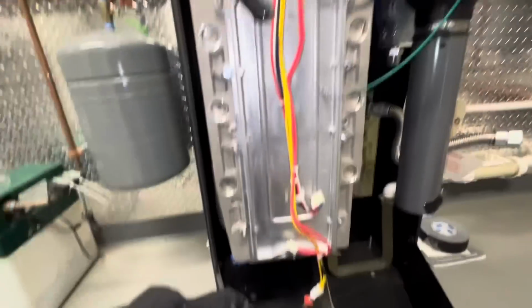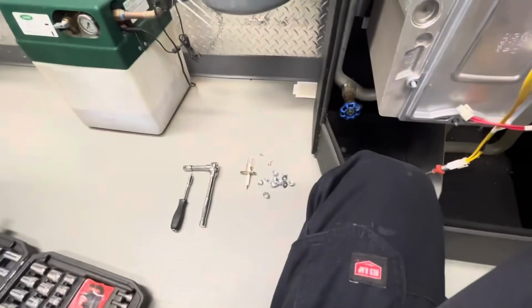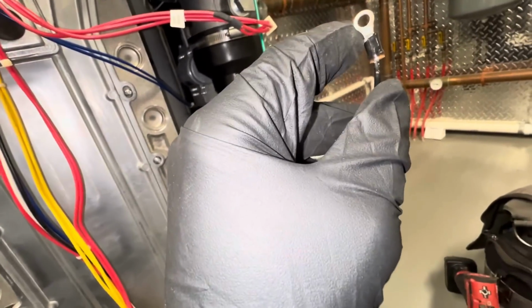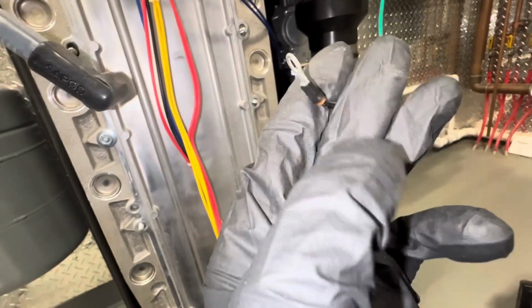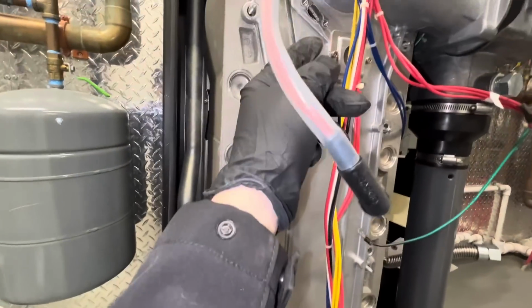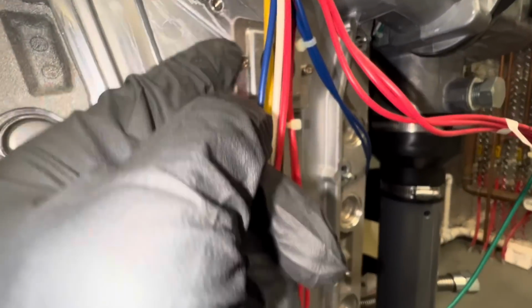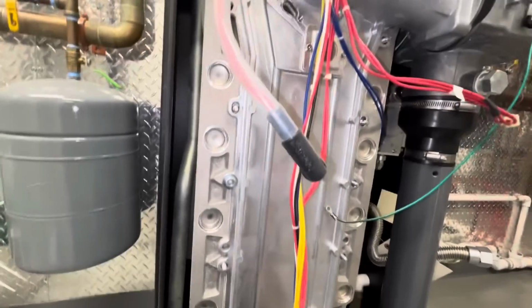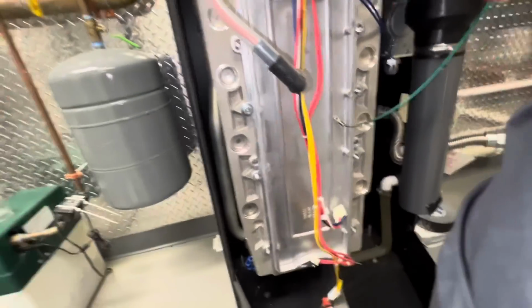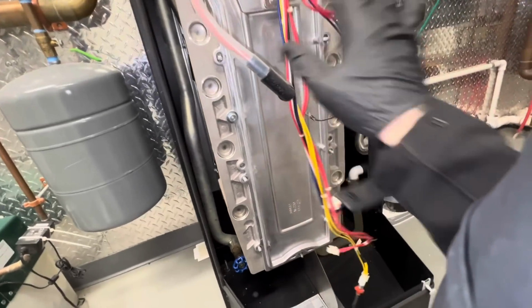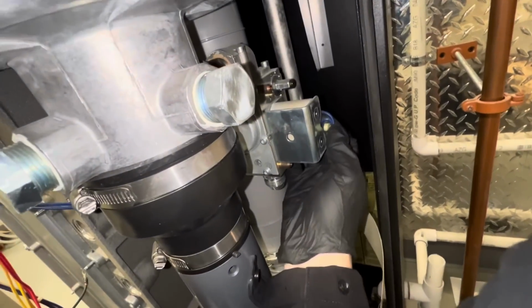Okay, so you can see there I pulled off my igniter, took all these 11mm bolts off from around the unit, and part of what's on the igniter screws, the hex head screws, is this grounding terminal, and you can see it gets very charred and burnt. This happens on all of them because some flue gas, I believe, makes it past this gasket, and they do give you a new gasket. I think if you replaced that regularly it would prevent that, but most people wait a while before they get their system's maintenance done.